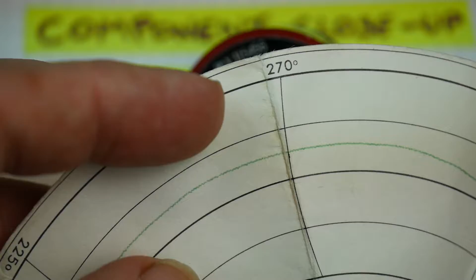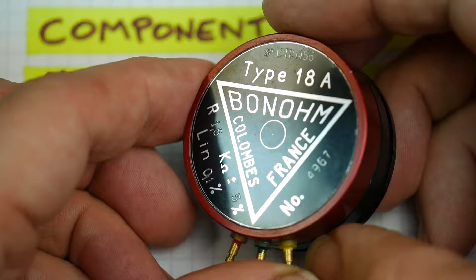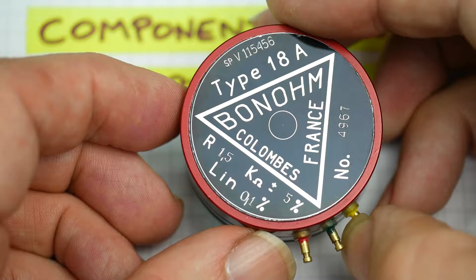As this thing has been calibrated, it veers off a little bit. So now we're not quite accurate, not perfectly accurate, but we're still within 0.1%, still within 1 part in 1,000 of the correct value of resistance for that amount of rotation. And then it veers back on again, and now we're back down to the 0 point. So you get an individual calibration certificate for this particular pot. It comes with it, folded up in the box. And when you fit the pot to your device, you know that the correspondence between resistance value and angular position is within 1 part in 1,000, 0.1%. So there we have it.